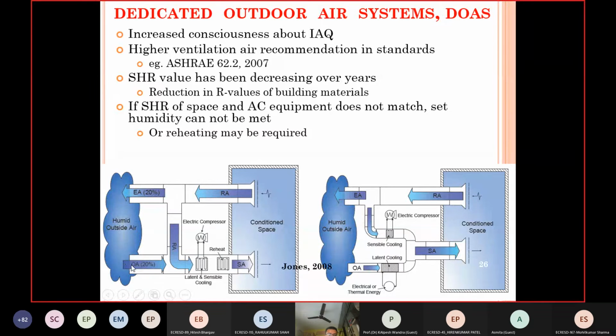So here in the conventional system, what is many times done is you want to take some fresh air, outside air, to be supplied into the conditioned space, and this is the return air coming from the conditioned space. Now the space is maintained at lower temperature and lower humidity levels, so the air here has very low enthalpy. But then when you're taking fresh air, you have to exhaust an equivalent amount of air. As it is shown here, this has low enthalpy, and you are just exhausting it.